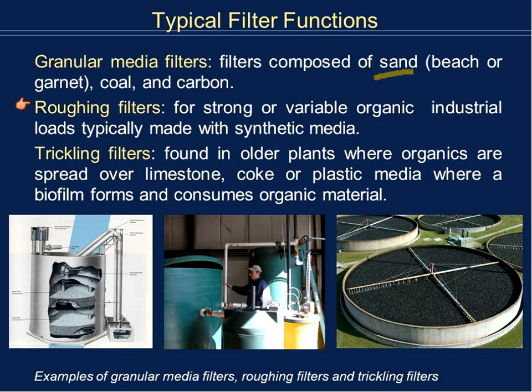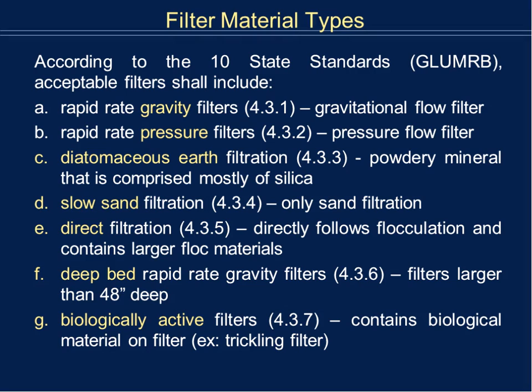Another type of filter is the roughing filter, typically used when you have a strong or variable organic load; you typically use a synthetic media — more like a small plastic, not sand. Last but not least is the trickling filter, typically found in areas where you have a large amount of area available. If you have a lot of real estate, you can have multiple trickling filter tanks. We don't see this often in New York City because real estate is very expensive, but if you go to northern New York State or just out of the state, this is very common, especially for older plants.